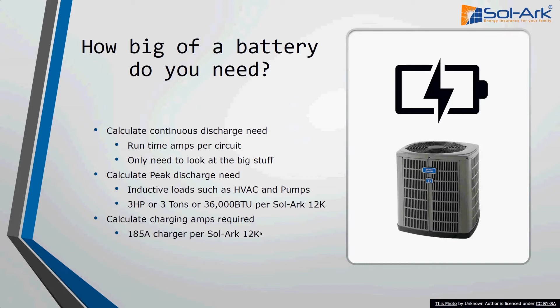Here I have a bunch of common appliances and an amp hour rating at 48 volts for each. So what this means is if you have 1 ton of AC, you tend to need about 150 amp hours of battery to support that. If you had 2 tons, you'd need 300, and so on. That's how to use these recommended values.